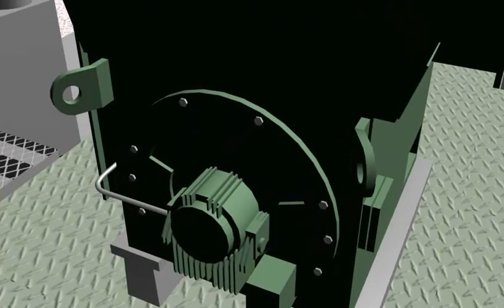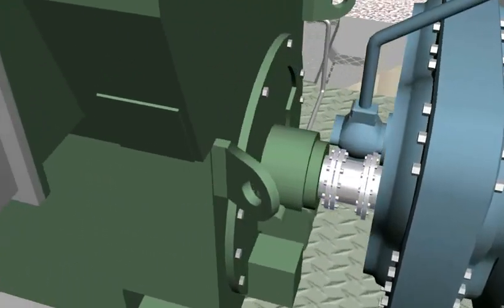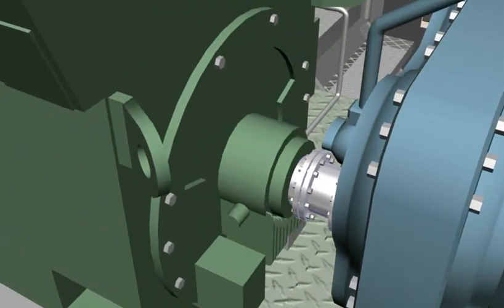The starting motor has a design limitation of 20 minutes between starts and no more than 4 starts per hour. Turbine lubricating oil is supplied to the motor bearings for lubrication.